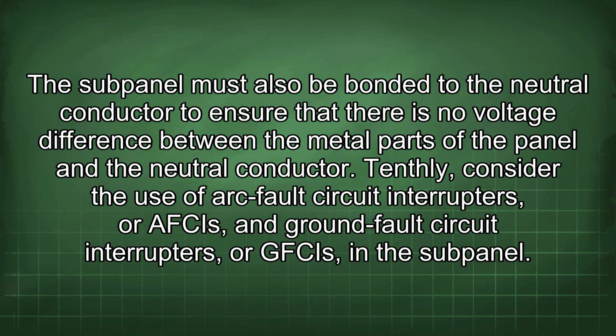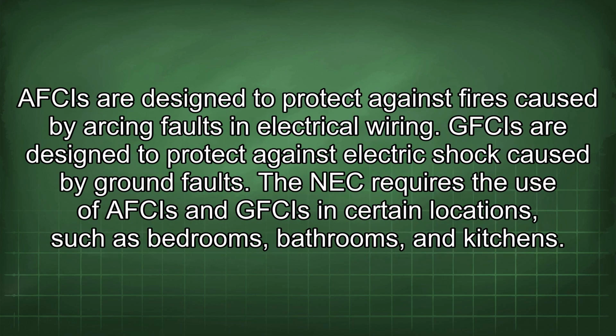Tenthly, consider the use of arc fault circuit interrupters, or AFCIs, and ground fault circuit interrupters, or GFCIs, in the subpanel. AFCIs are designed to protect against fires caused by arcing faults in electrical wiring. GFCIs are designed to protect against electric shock caused by ground faults. The NEC requires the use of AFCIs and GFCIs in certain locations, such as bedrooms, bathrooms, and kitchens.